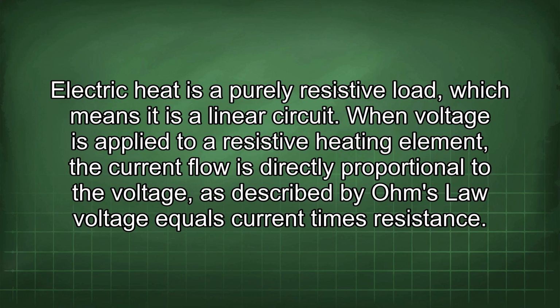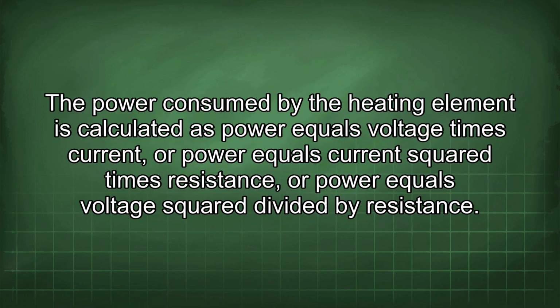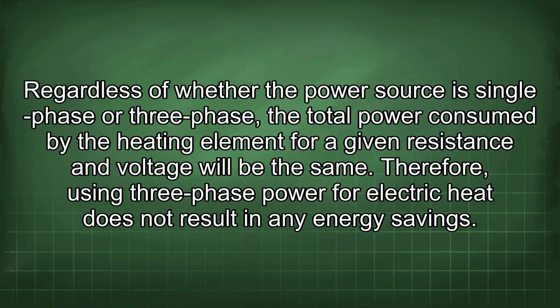Electric heat is a purely resistive load, which means it is a linear circuit. When voltage is applied to a resistive heating element, the current flow is directly proportional to the voltage, as described by Ohm's law: voltage equals current times resistance. The power consumed by the heating element is calculated as power equals voltage times current, or power equals current squared times resistance, or power equals voltage squared divided by resistance. Regardless of whether the power source is single-phase or three-phase, the total power consumed by the heating element for a given resistance and voltage will be the same. Therefore, using three-phase power for electric heat does not result in any energy savings.